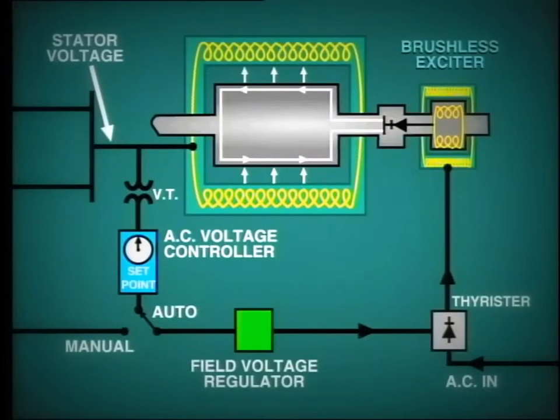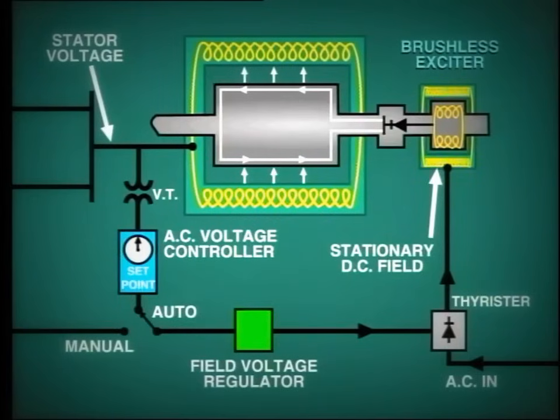In this exciter, a stationary magnetic field is provided from the DC winding, which is wound on the stator. The rotor winding produces AC voltage and this is fed directly into diode type rectifiers, which are built into the shaft. So we have in effect a rotating rectifier.